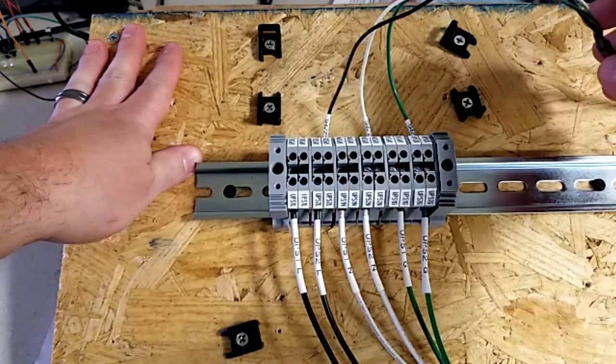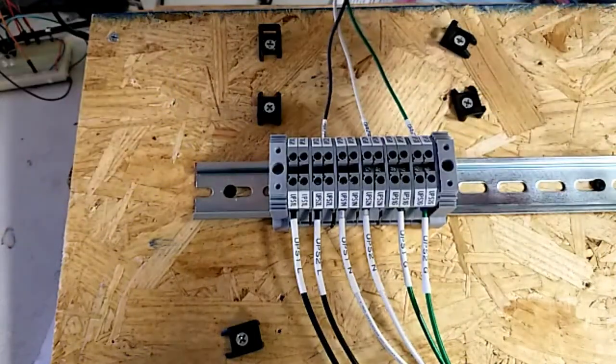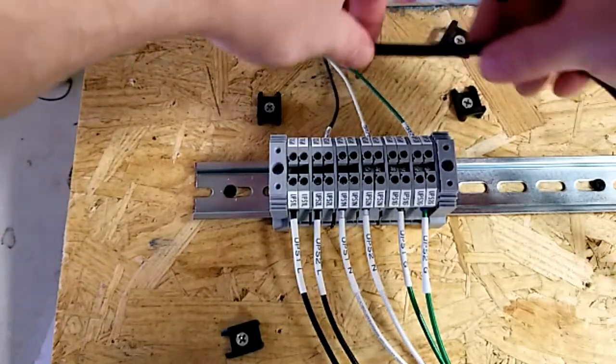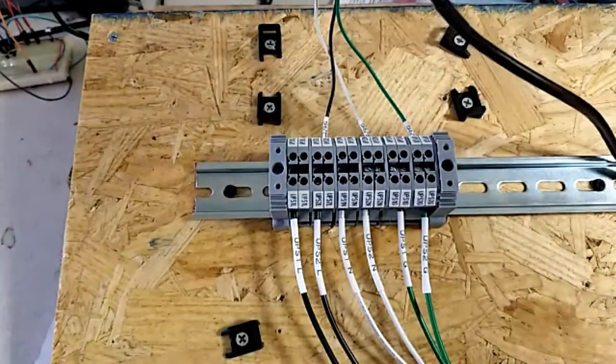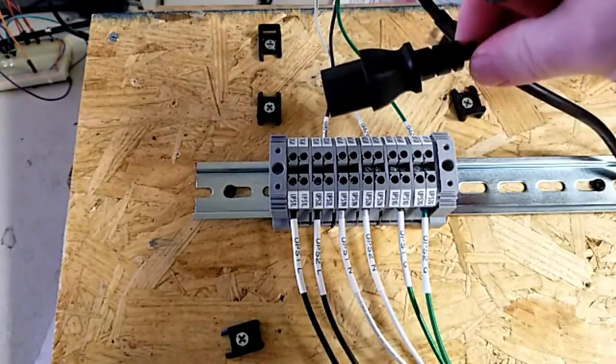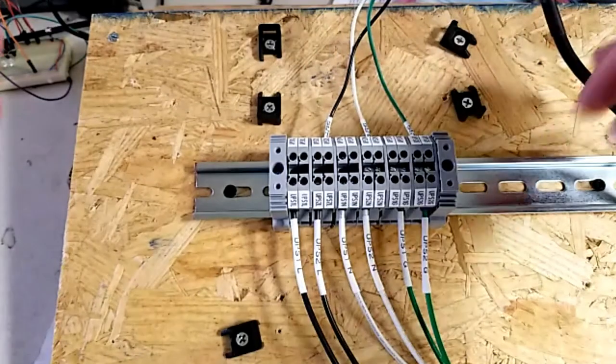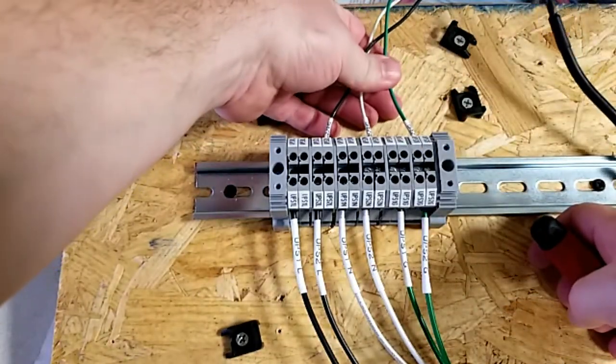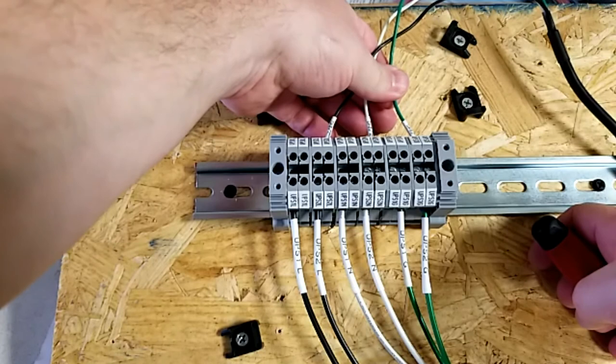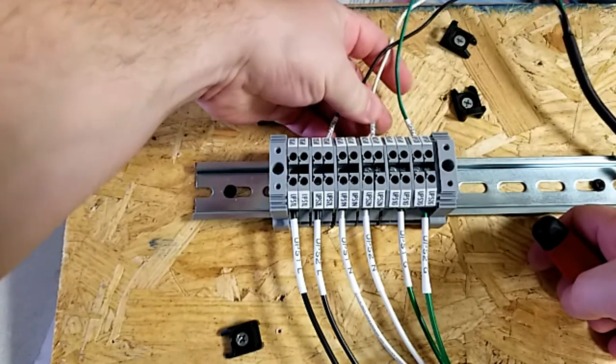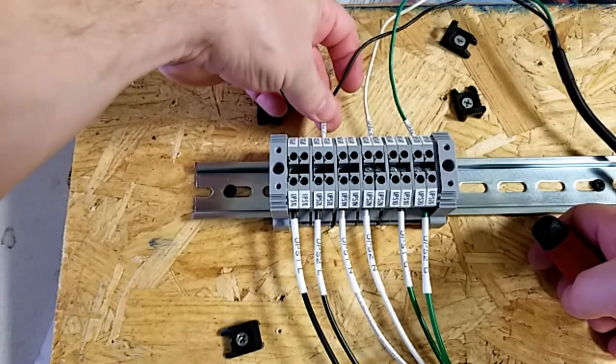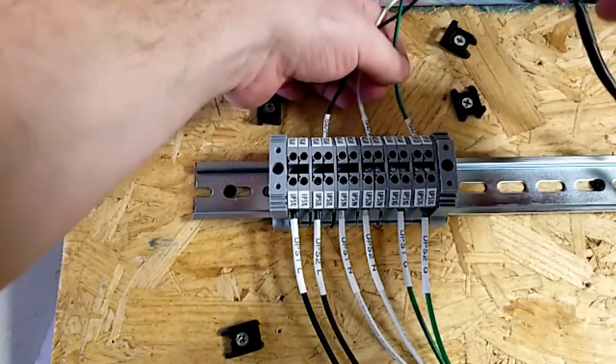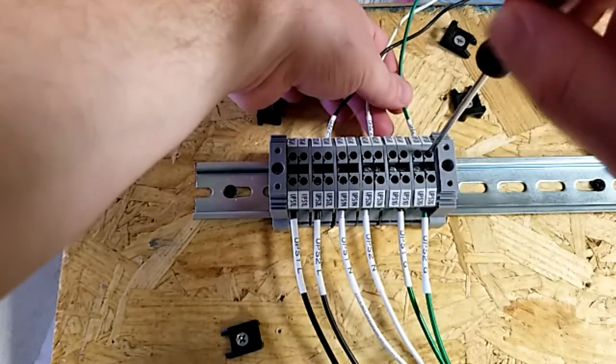So first thing we're going to do is we're going to unwire this power cord. So you'll see that it's three wires, but it goes into one power cord with a standard IEC computer-style connector on the end of it. So first thing we're going to want to do, this should be labeled PC4 power, and then it'll be UPS2G for ground, UPS2N for neutral, and UPS2L for line. So we're going to unwire the three PC4 power connections here.